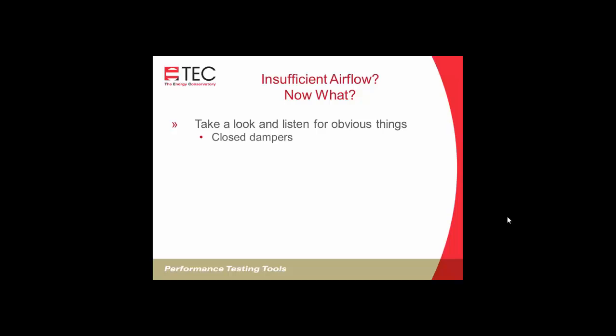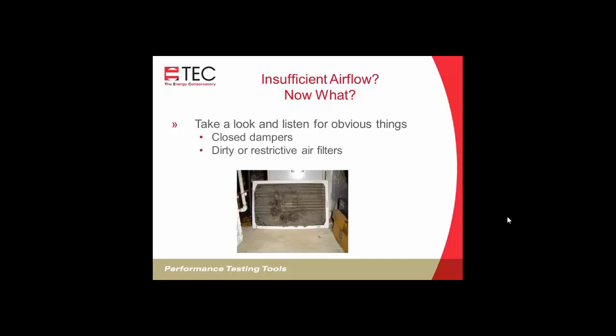Some other obvious things, closed dampers. If they're trying to push air to a room over a tuck-under garage, maybe there's some bedrooms over a garage that are the farthest away from the furnace, and maybe you're not getting enough airflow there, so you're choking off all of the other dampers to try to force air out over that space that's not heating or cooling properly, and that may be causing enough of a restriction where you're getting high static pressure and low airflow. Dirty or restrictive air filters are certainly an issue, so check and make sure they're clean, and if you've got some pleated filters, sometimes they're just too restrictive for the amount of airflow. So some pretty obvious things.